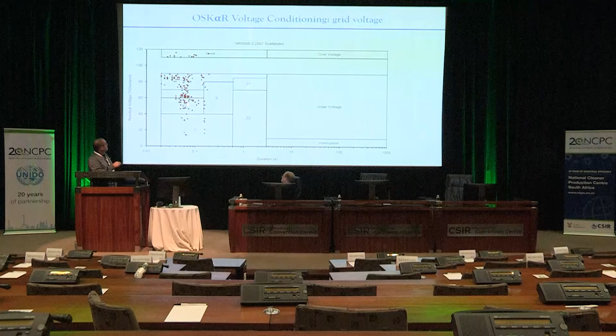Time is on this axis, logarithmic, showing a reduction in voltage. The idea is voltage should remain within 110 and 90% of the value regarded as nominal. So variations should sit here, and that's how networks should be operated. But faults occur, and this was not over a very long period - each of these is an incident where a so-called dip is measured due to a short circuit somewhere.